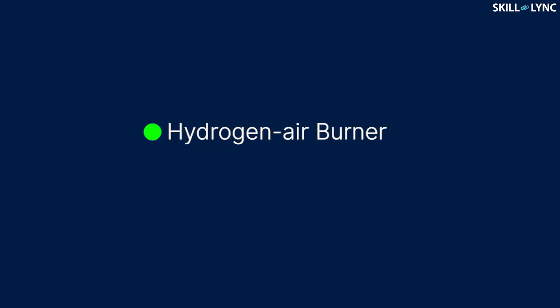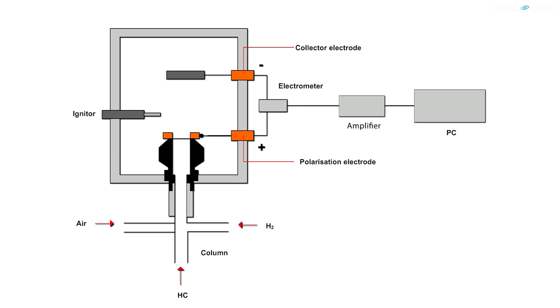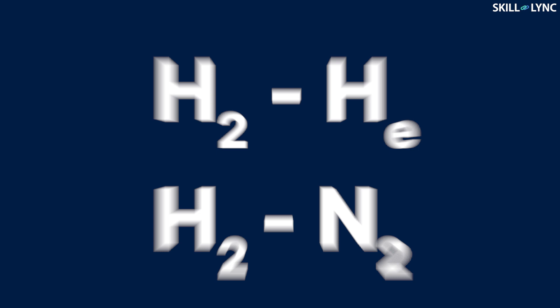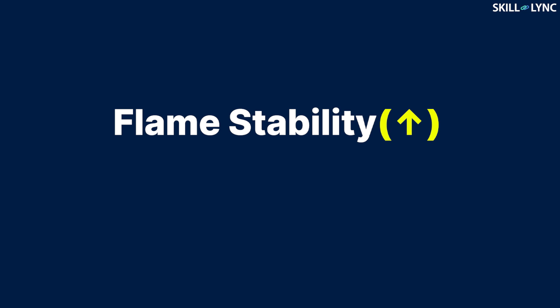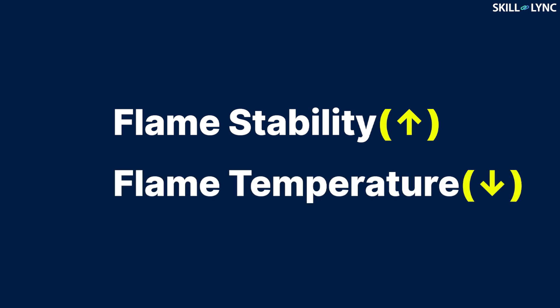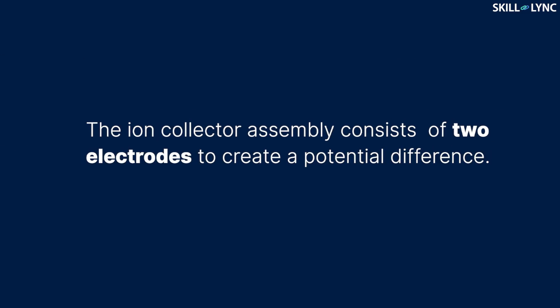When it comes to construction, the FID analyzer consists of a hydrogen-air burner and ion-collector assembly. There are individual inlets for hydrogen and air. Instead of hydrogen, hydrogen-helium or hydrogen-nitrogen mixtures can also be used for improving the flame stability and for decreasing the flame temperature. There is also a column through which the sample of the exhaust to be tested will be fed in. Then, there is an igniter which is used for ignition.